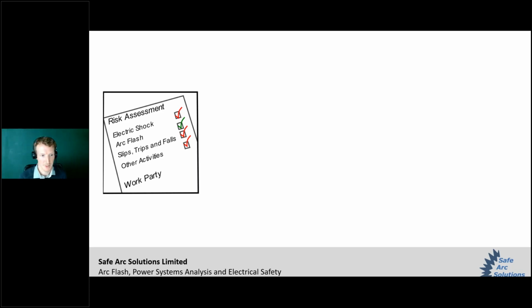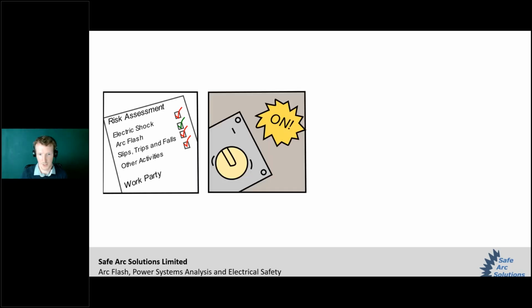Down at the switchboard, the risk assessment's reviewed. There's actually some labeling now on the equipment, and this confirms the findings of the risk assessment and identifies those mitigations. So Scott goes away and turns on the maintenance mode by turning on this key switch adjacent to the switchboard, and then he and Sam put on their balaclavas, put on a face shield, and add some gloves to the daily wear Arc Flash PPE coveralls that they're already wearing. You're not involved in the task, so you're asked to stand well back beyond that 5 meter line and told to make sure no one comes any closer.